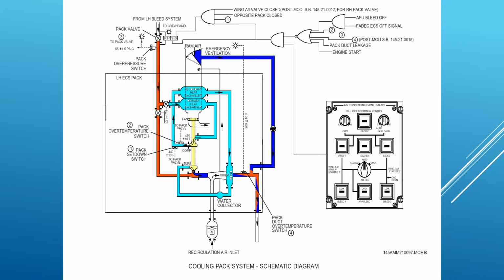The next thing it comes to is this dual temp control valve. What you see here is 2 physical valves, but actually 1 unit, controlled from a single torque motor. This is our temp control valve. You can see in the picture there's 2 valves, it would appear, but as I said, they are mechanically joined together, so when one valve opens, the other valve will close.